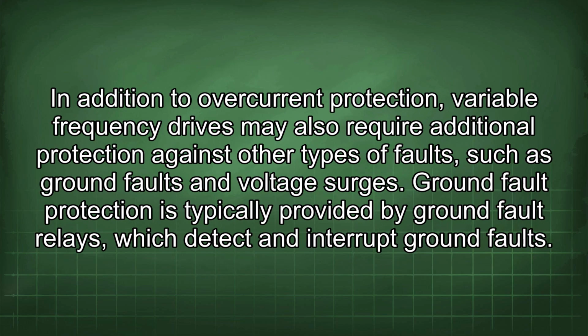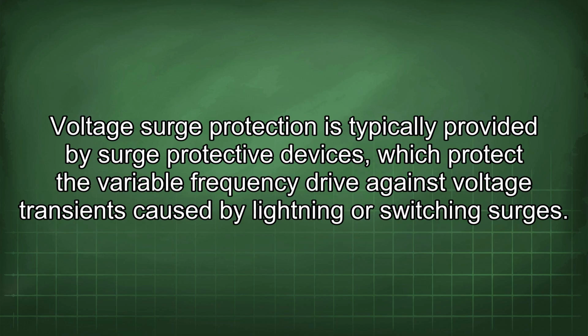In addition to overcurrent protection, variable frequency drives may also require additional protection against other types of faults, such as ground faults and voltage surges. Ground fault protection is typically provided by ground fault relays, which detect and interrupt ground faults. Voltage surge protection is typically provided by surge protective devices, which protect the variable frequency drive against voltage transients caused by lightning or switching surges.